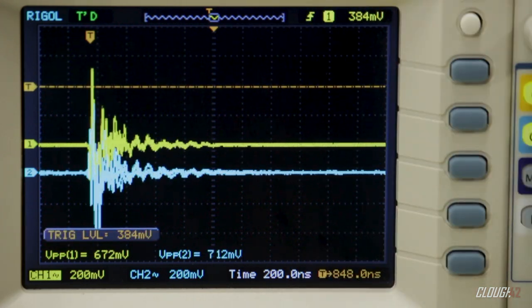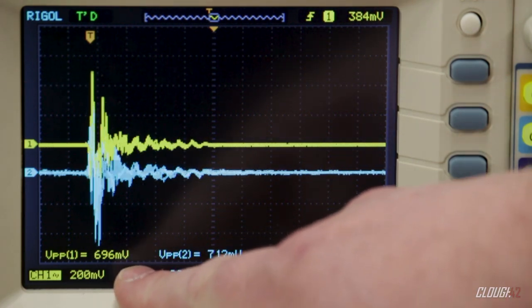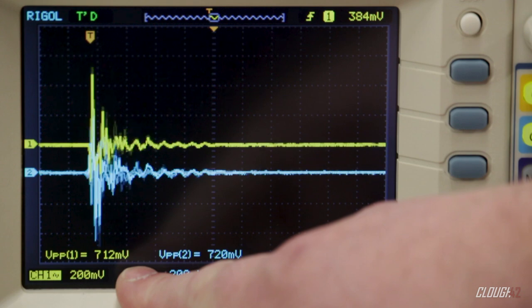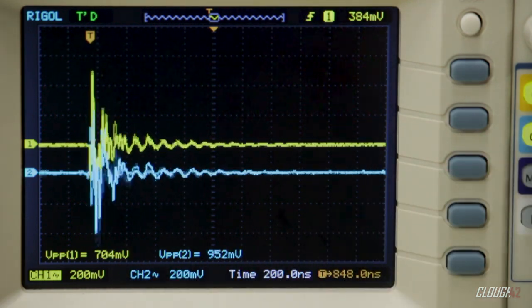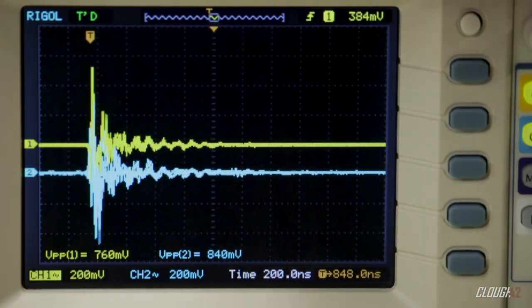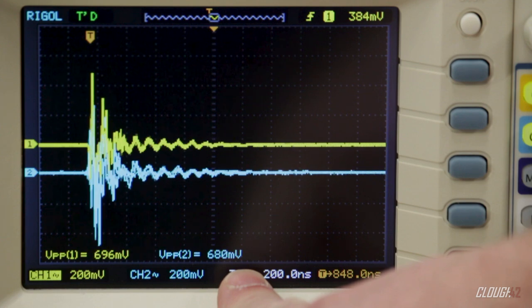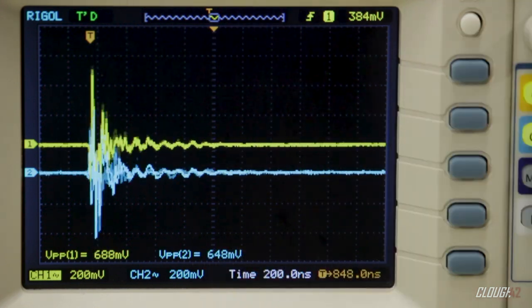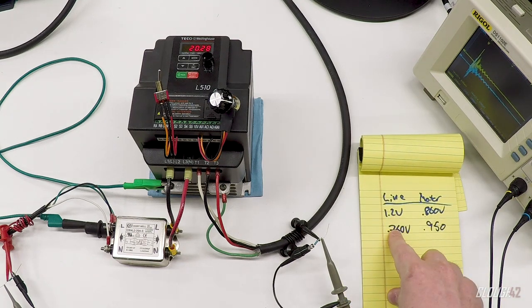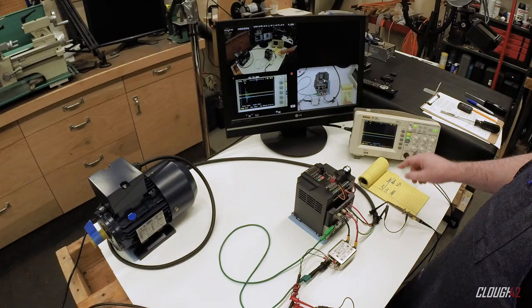It looks like the peak to peak voltage, I'm watching this on the line cord and I'm seeing I think about 760 is the highest number I've seen. And over here on the motor lead, I'm seeing maybe 900, 950 millivolts. So you can see we've cut almost in half the conducted noise going back up the line to the monitor.